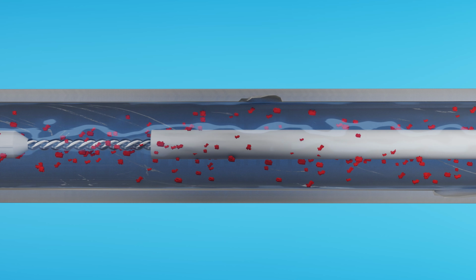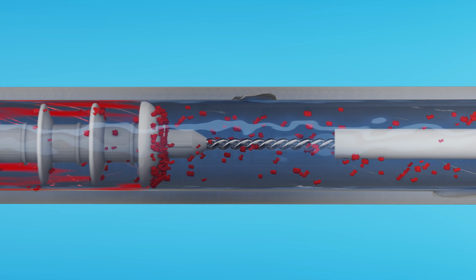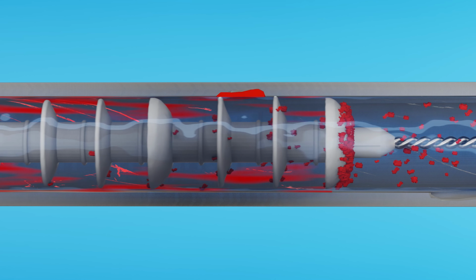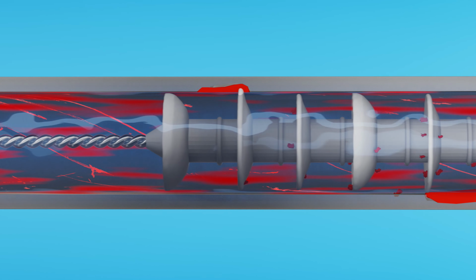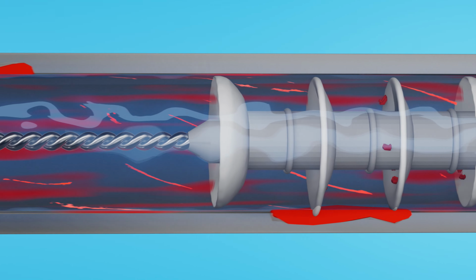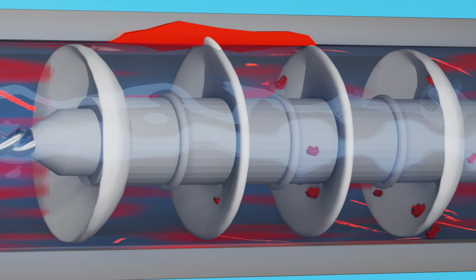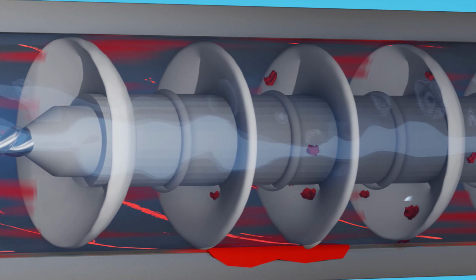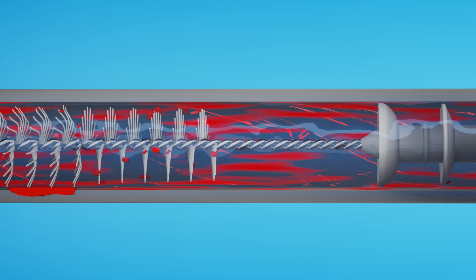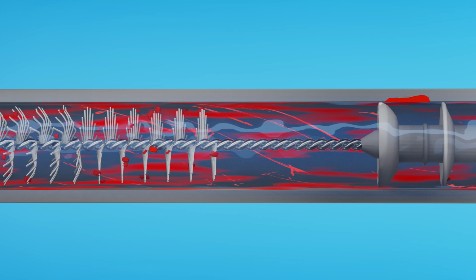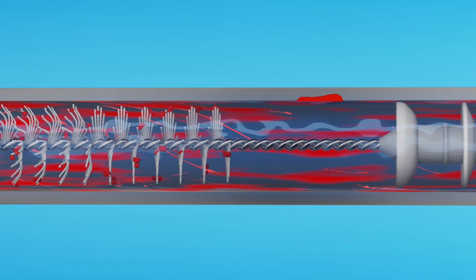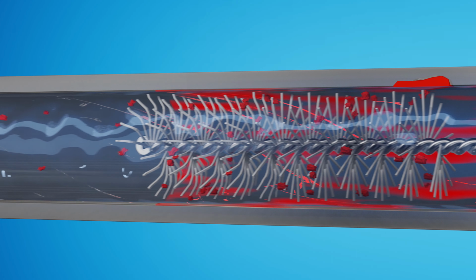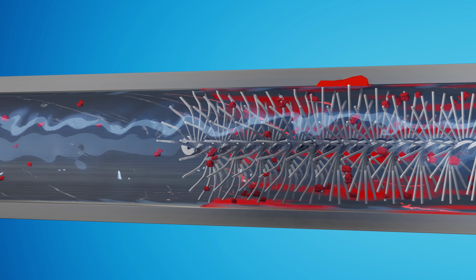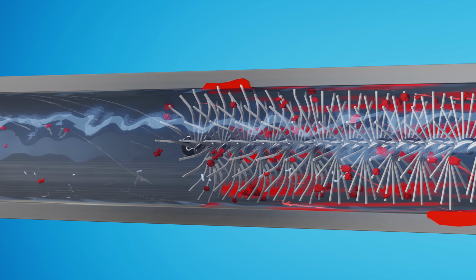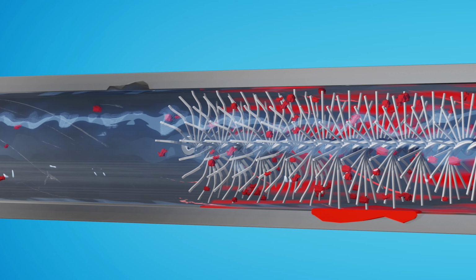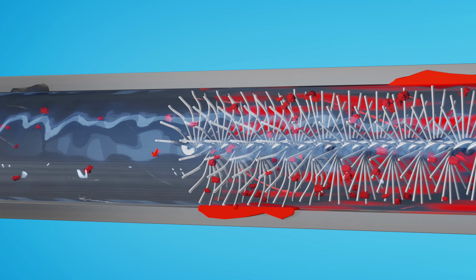It is important to note that squeegees alone cannot remove debris from scratches or other imperfections. Instead, they may inadvertently deposit bioburden into these voids. Squeegees also leave behind a very thin invisible layer of biofilm on the channel's walls. The tail brush, constructed with fine bristles, addresses this challenge by brushing away the residual debris from the voids and scratches and effectively removing the biofilm. It is a unique feature of the SuperDART.